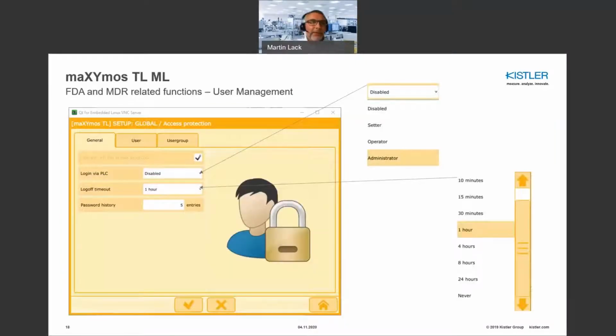Now we come to the FDA and MDR related functions in the maXYmos TL ML. The TL was developed and improved to reach the ML functionality by adding user management, so we can add users to the maXYmos TL ML. These users can be disabled or set up by an administrator, and are locked out after a defined time which the administrator can adjust. Each user needs a password, and this password expires.